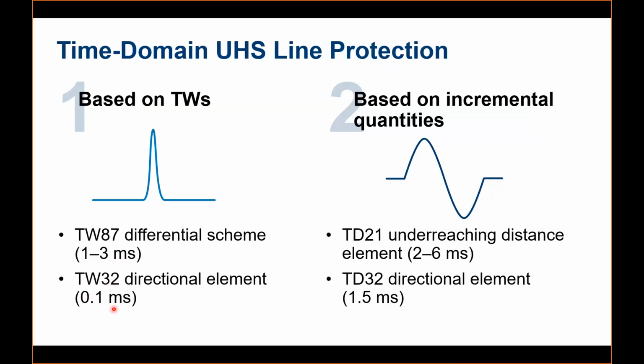TW32 is much faster, it even responds in 0.1 milliseconds. So you can just think about 0.1 milliseconds as compared to the normal directional elements. The TD21 distance elements are much faster than the conventional distance elements. They respond in 2 to 6 milliseconds, depending on the fault location on the line. If it is closer, it will act faster. And if the fault is away from the relay, it may take a little bit more time. Another directional element that is incremental based is also very fast, and you can implement these 2 elements in your POTT schemes for very reliable and fast permissive schemes.